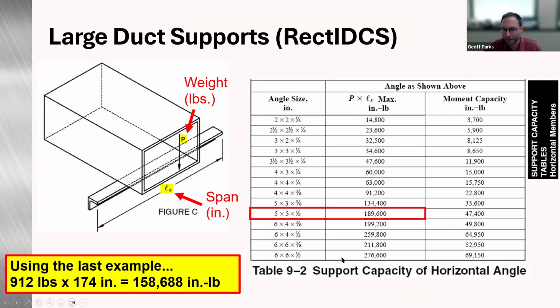So coming over to this table 9-2 support capacity for horizontal angle, this is telling us we would need 5 by 5 by ½ inch angle versus the 3 by 3 by ½ inch. So as you can see, it significantly reduced our angle size requirement for that trapeze. But this is also an acceptable way to size that support as well.